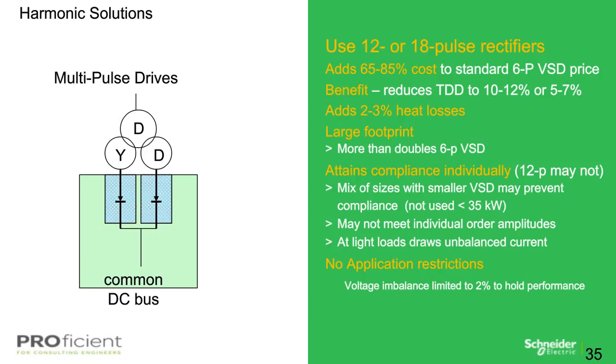Both solutions are fairly physically large with the auto transformers. It essentially doubles the size, again using a standard 6-pulse VFD as the benchmark. Due to rising cost factors as the size of the VFD is reduced, they are not typically applied below 75 kW or 100 horsepower. However, when the load is reduced, the input current typically goes unbalanced on the secondary windings, reducing the percent THDI benefit. So when the AC goes unbalanced, the percent THDI reductions are minimized, thus having fairly poor percent THDI results. And as far as application limits with the multi-pulse drives, there's really no limits. As far as voltage imbalance, added losses of 2 to 3% are typical within auto transformers.